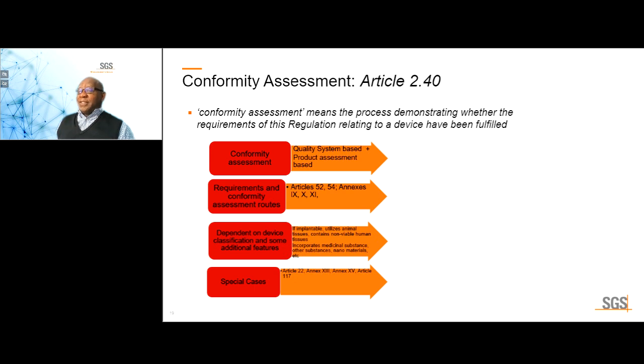Conformity assessment under the European system always involves 2 strands of evidence: quality system-based plus a product-based assessment. You need these 2 strands of evidence for your device to be certified. And you must demonstrate compliance with each set of requirements, i.e. QMS-based requirements and product assessment-based requirements. And the requirements and conformity assessments are in Articles 52, 54. This is where you can find out what it's all about. And then Annexes 9, 10, and 11 tell you how to go about demonstrating compliance.